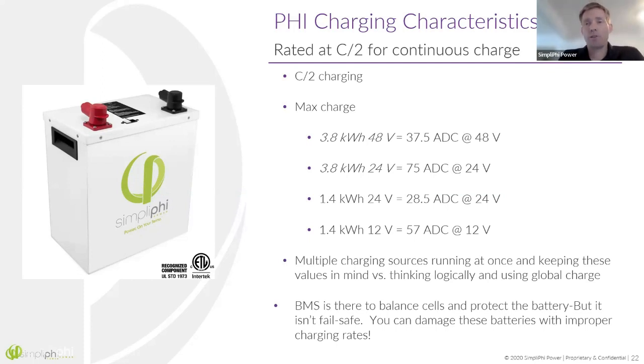So with the 24-volt option, you can actually charge it a bit faster because it has a larger current capacity. It has a larger total charge capacity. And so you can charge that one at 75 amps for the 24-volt option. That's per battery again. And then the smaller format batteries, the charging rates are specified there. So do be careful if you have multiple charging sources running at the same time. So we'll sometimes get people that have 3 or 4 charge controllers all running at the same time. They've bought one and then they've upgraded their system and buy another out back or something like that. So just keep in mind that you have to pay attention to the maximum output of each of those. So if they're all going at the same time, you could damage the batteries if they're not properly programmed.